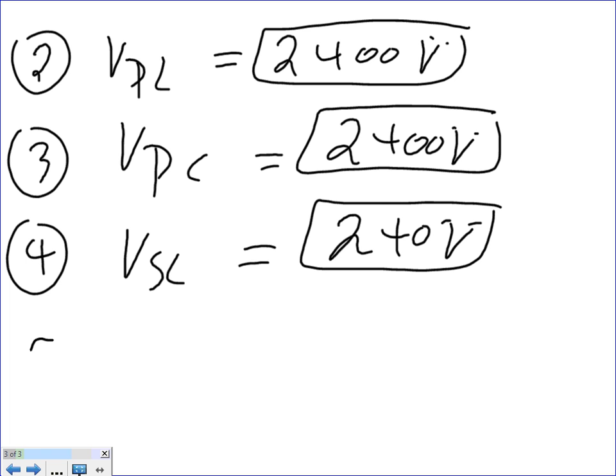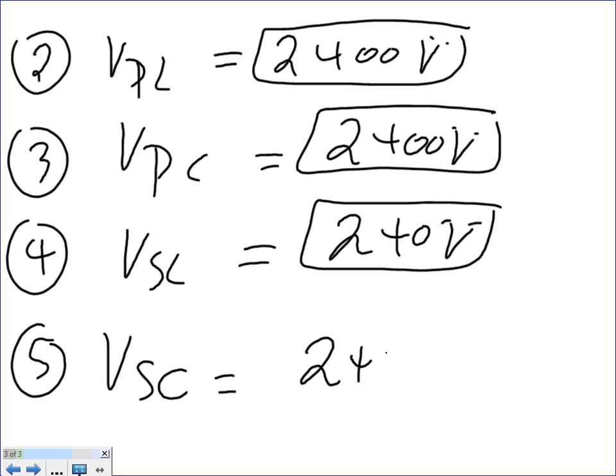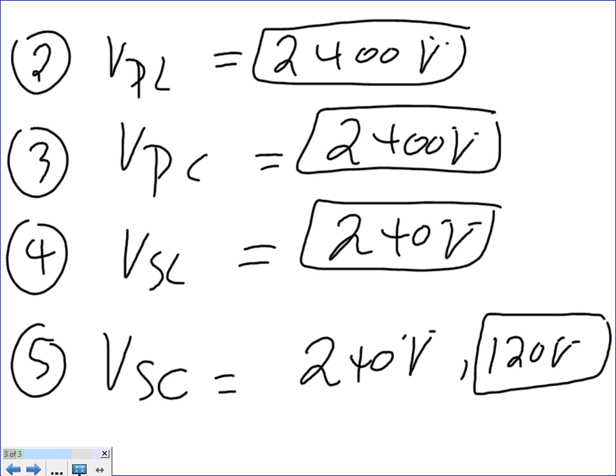And voltage number five is voltage secondary coil, or phase. That one is also 240 volt, guys, but they also have a 120 volt coil. So two voltages, because we have two voltages on the coil side: a 240, like a delta, and also a 240/120 volt. The 120 is coming from the center tap. Any question, guys? So I went fast through that one. That's straightforward, it's the delta, just writing the information about the voltage line and coil.